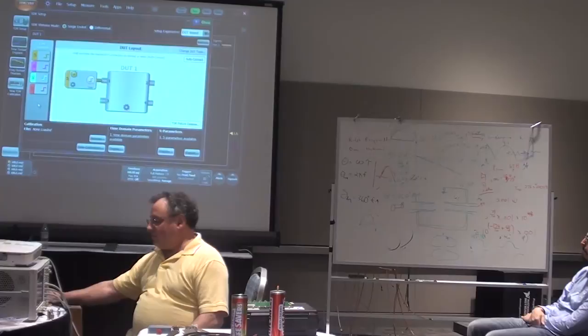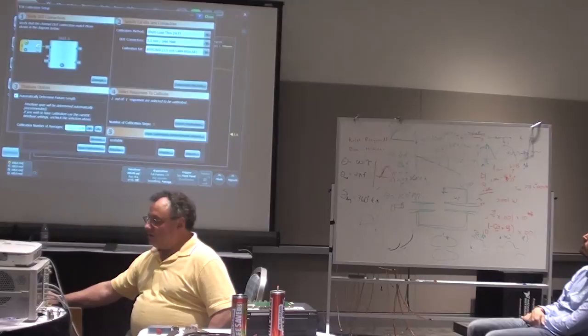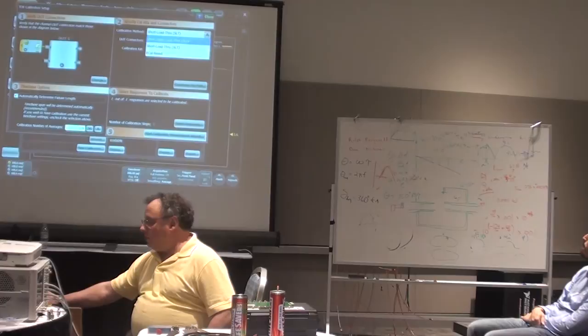So that's all really good. And at this point here, I want to make a new calibration, so it's got this little business down here to do that. And it takes you through what they call the wizard. It says you've only got one guy, which is good. And then we want to know what kind of calibration we can use. Well, here's what we got. Options are ECAL, short load through, or short open load through.